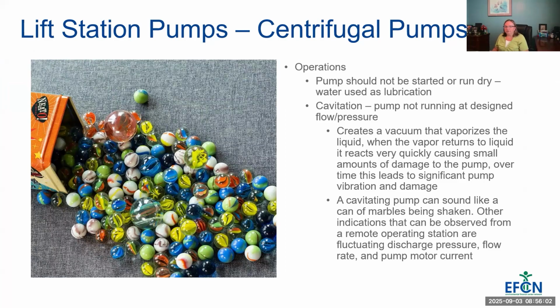When you're operating a pump, you should never start it or run it dry. The water is used to lubricate your parts in your pumps. So if it's dry, it can overheat very quickly and cause all kinds of problems. Cavitation is another issue with centrifugal pumps. Whenever the pump's not running at the designed flow or pressure, cavitation can occur. This is where a vacuum is created and the water vaporizes. And when it returns to a liquid, it's damaging to the pump. It's like little bullets of water shooting your pump parts, and it damages your pump.